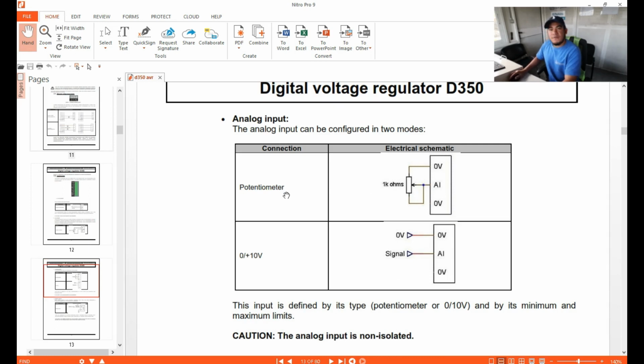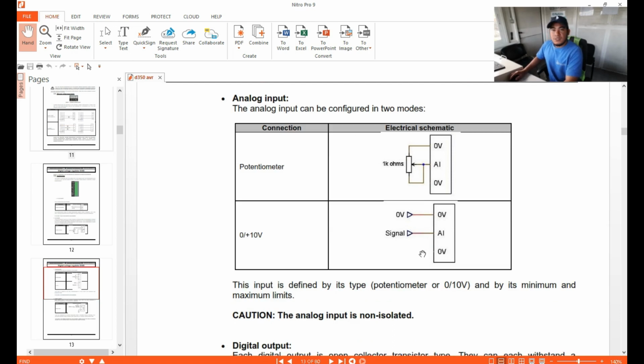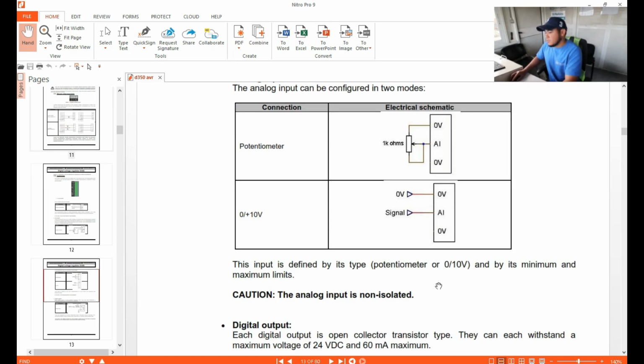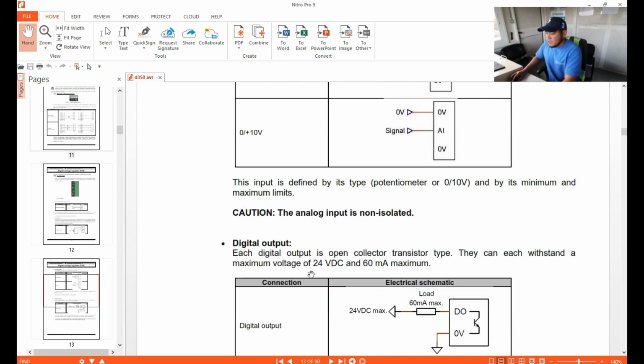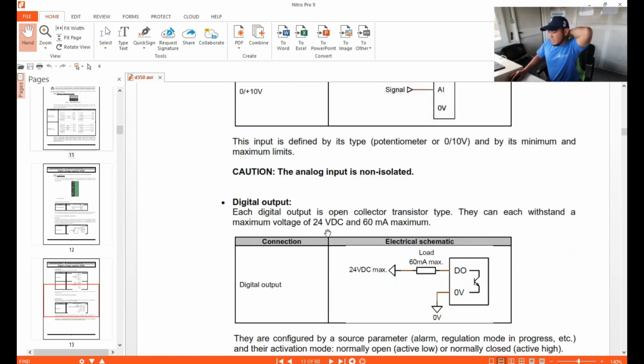So you can use this one if you have the voltage potentiometer, where you can adjust your voltage externally, and also you can use this one if you have the analog configurations for the paralleling. So here you can connect those wires for your signal through your module. This one is your AVR side for your module, where you can connect to 0 to AI. Okay, but make sure to configure after those connections. Input defined by the potentiometer or 0 to 10 volt and the minimum and maximum limits. So analog input is non-isolated. Its digital out is controlled with a constant maximum voltage of 24 VDC, 60 milliamps maximum.